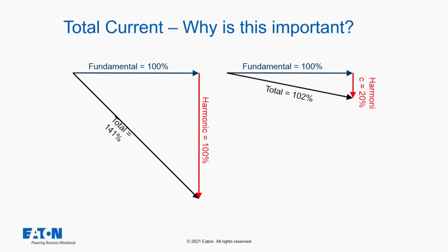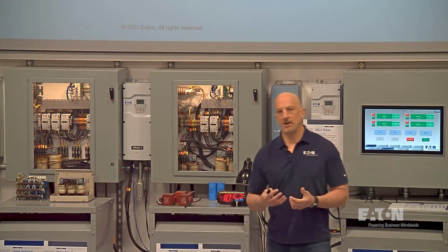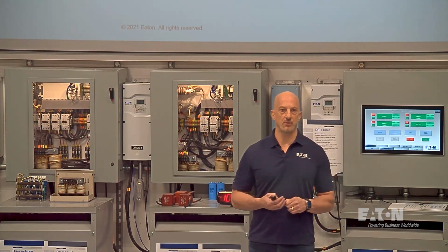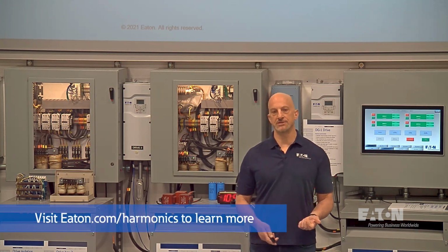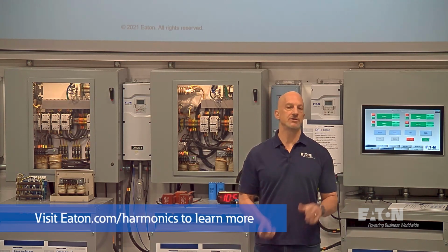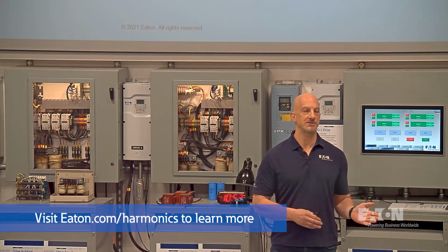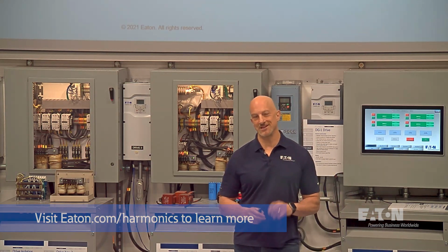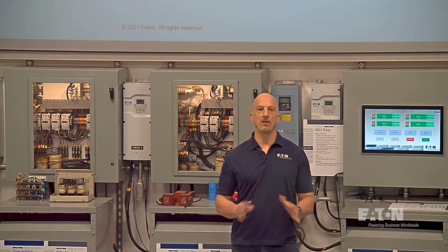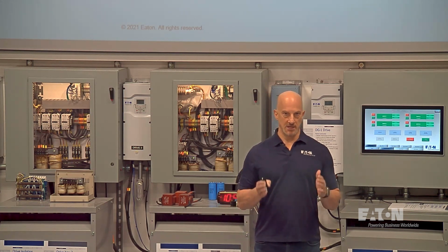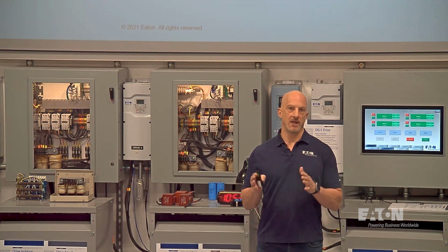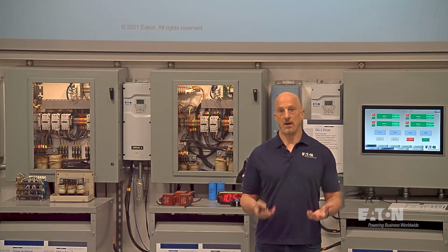A lot of people get concerned about, for example, 20% distortion. But if we have 20% distortion on a power system, we really only have about 102% actual RMS current. So if you designed your system to work at 100%, but it fails at 102%, it might be a little marginal. All of this comes into play when you analyze the waveform, trying to make sense out of how those harmonics add up on the power system.